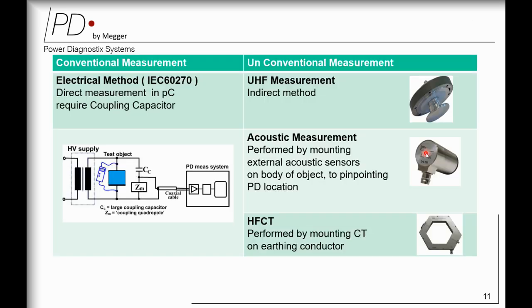Also, those measurements which we have discussed, which fall under electrical and mechanical, are divided into two different groups. One is conventional measurement, and the other is non-conventional measurement. Conventional measurement means the electrical method, IEC 60270, where you do the PD measurement in terms of picocoulombs using the coupling capacitor. This method is typically done in the factory during the factory acceptance test. Whereas when your GIS is assembled and on site, you cannot conduct the electrical method for routine maintenance and to check the dielectric strength of your material.